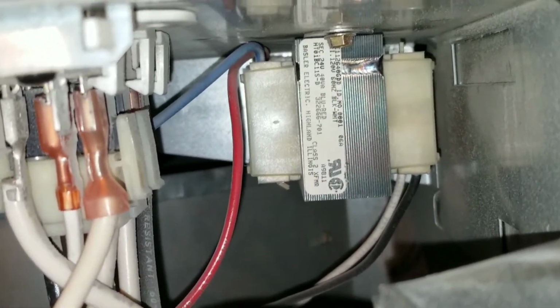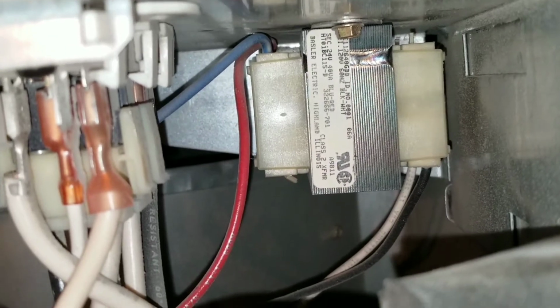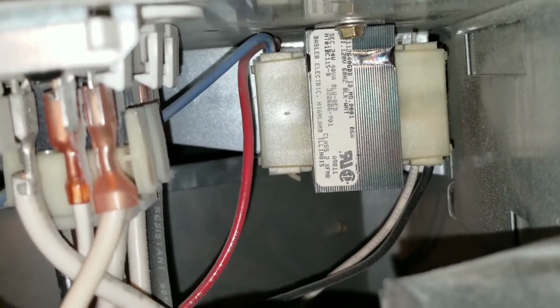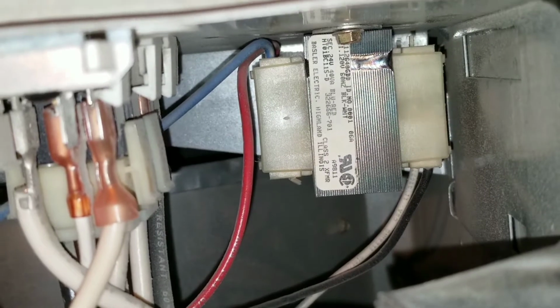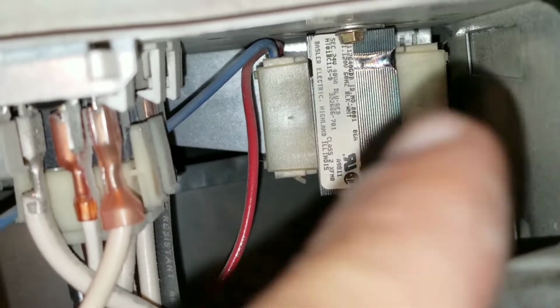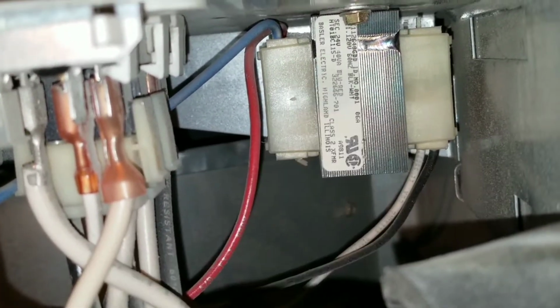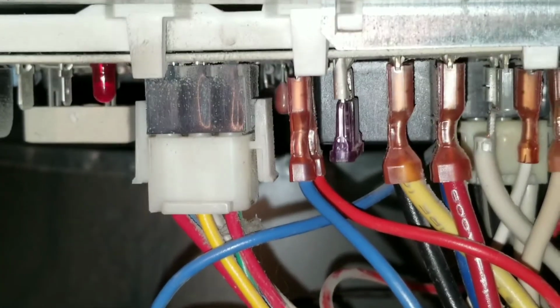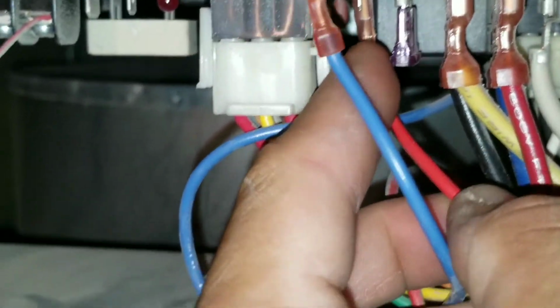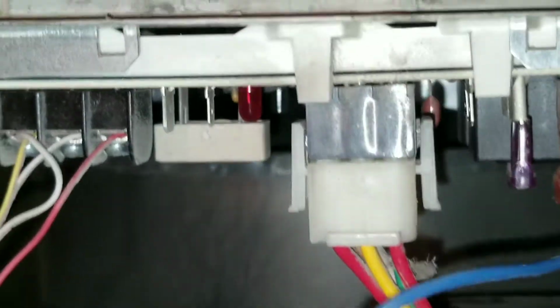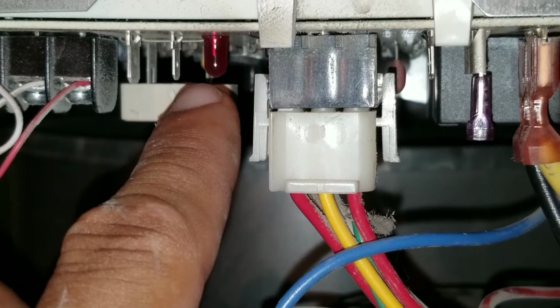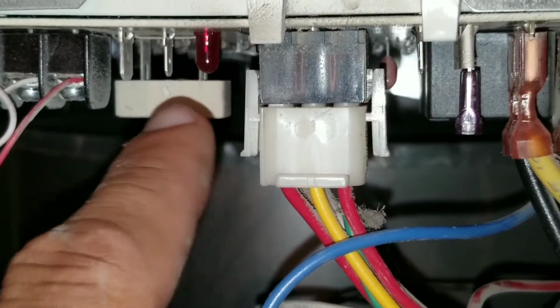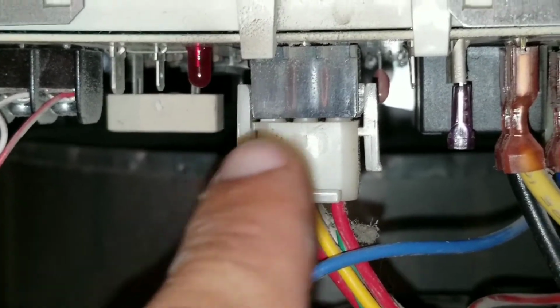You can see there on the transformer, if you're unsure, secondary 24 volt. And then it shows your blue and your red right there. If you lost power to your board, if you didn't have any power coming to this board, it would most likely be an issue with your transformer. So here I'm going to pull my wires, and you can see once I pulled my wires from my transformer, my LED light is no longer flashing, that's because right now my board doesn't have any power coming in.